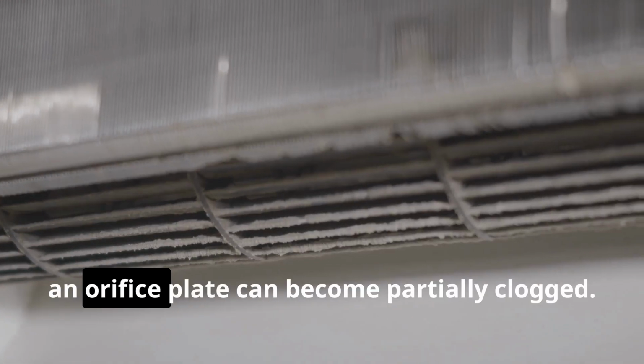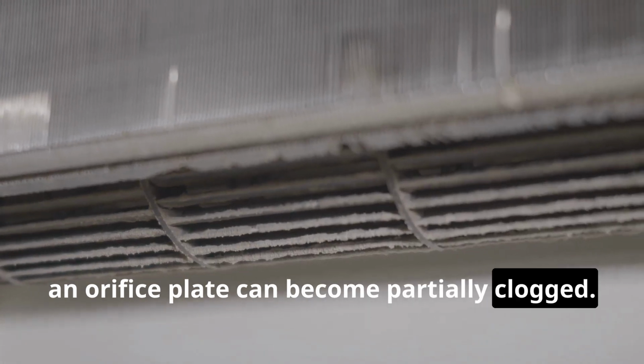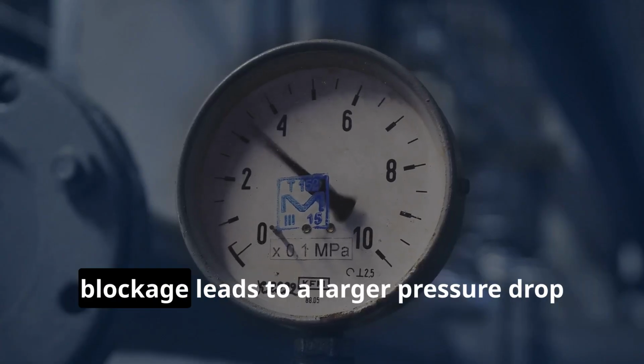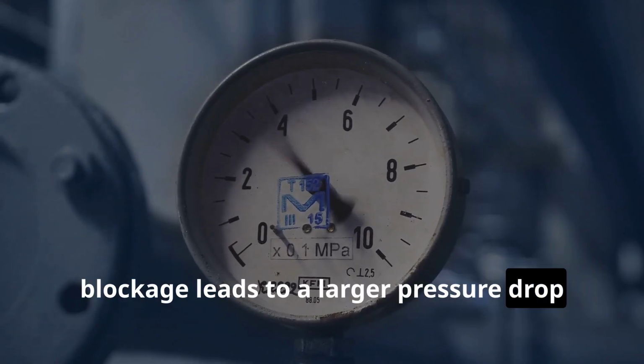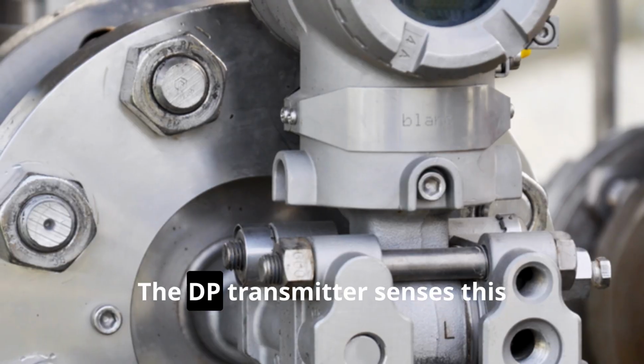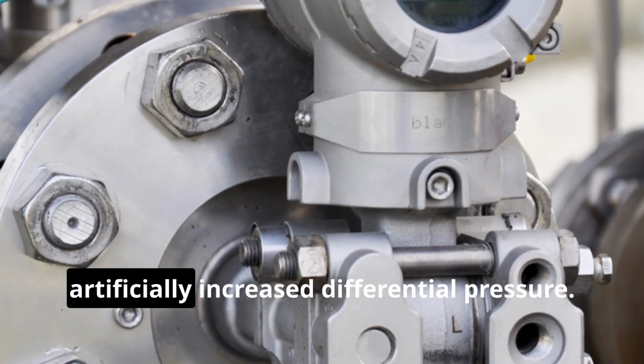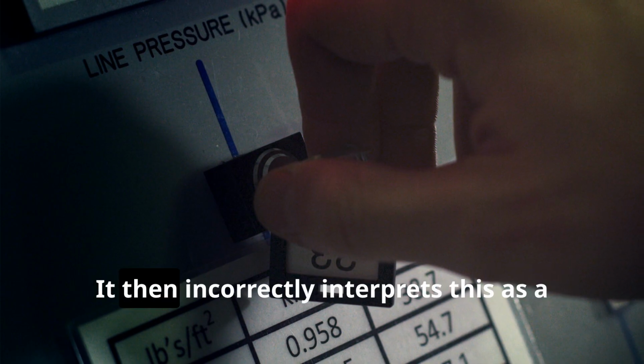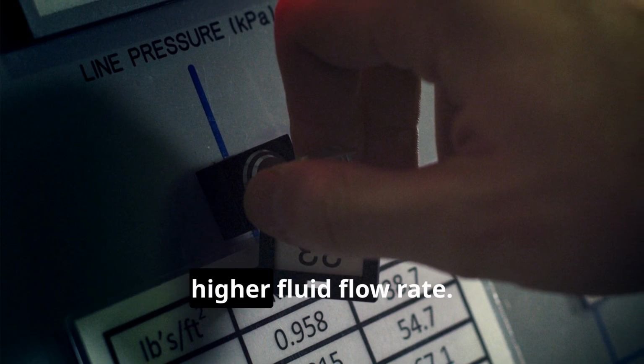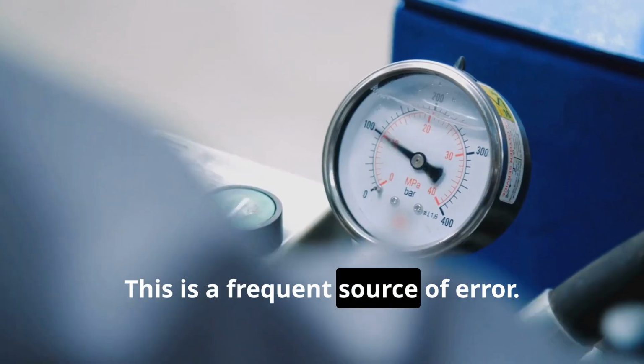For example, an orifice plate can become partially clogged. The increased restriction caused by the blockage leads to a larger pressure drop across the measurement points. The DP transmitter senses this artificially increased differential pressure. It then incorrectly interprets this as a higher fluid flow rate. This is a frequent source of error.